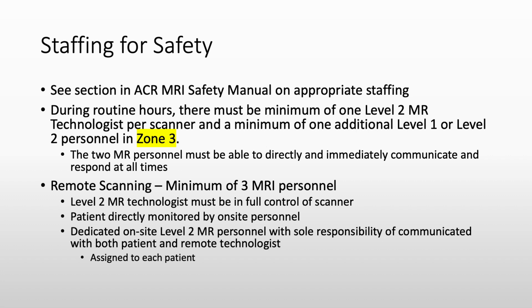The 2024 ACR manual prescribes minimum staffing levels. I recommend you review that section. During routine hours, there must be a minimum of 1 Level 2 MRI technologist per scanner and a minimum of 1 additional Level 1 or Level 2 personnel in Zone 3. These 2 MRI personnel must be able to directly and immediately communicate and respond at all times. Note that both of these individuals need to be present in Zone 3. One of these individuals cannot be in Zone 2.